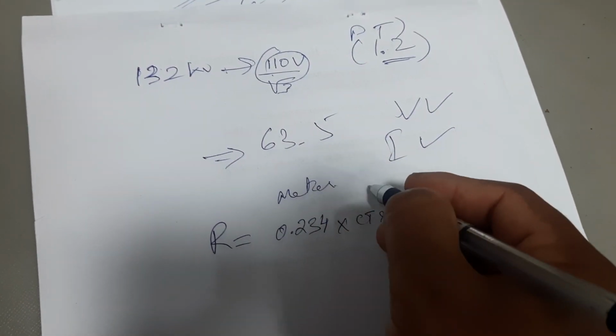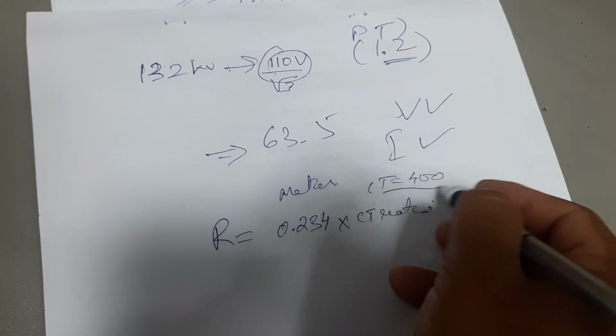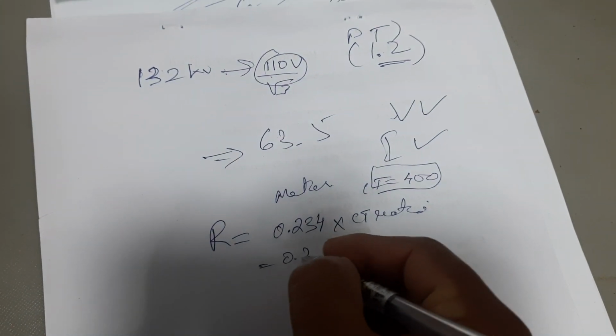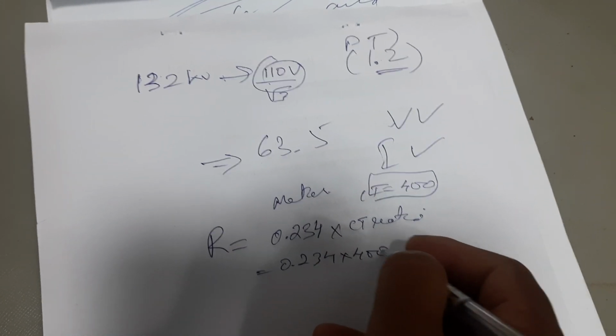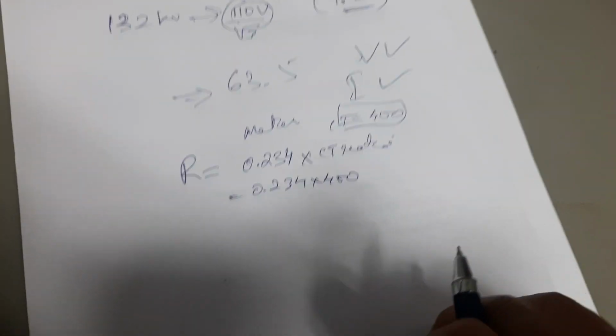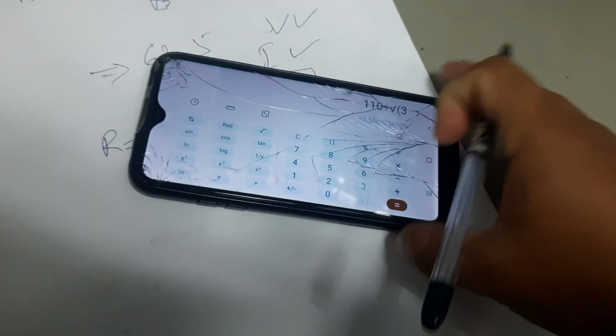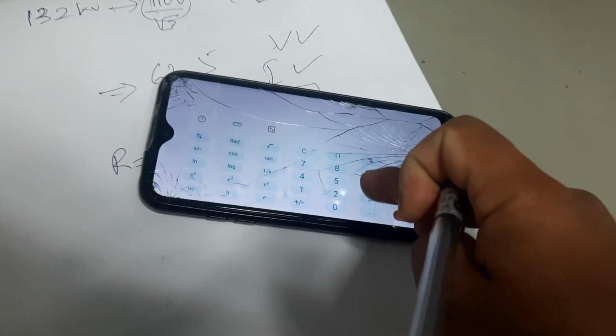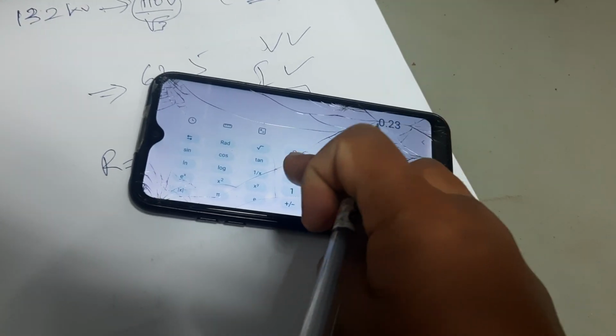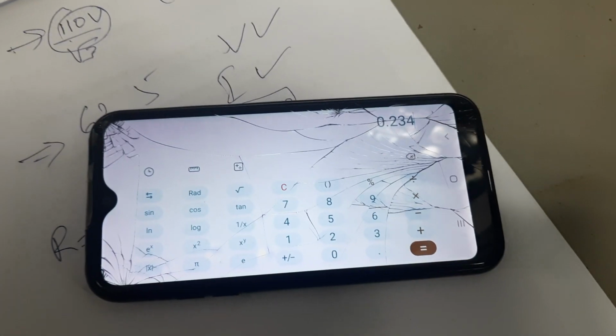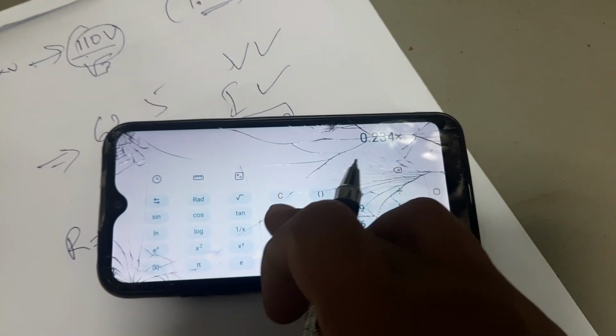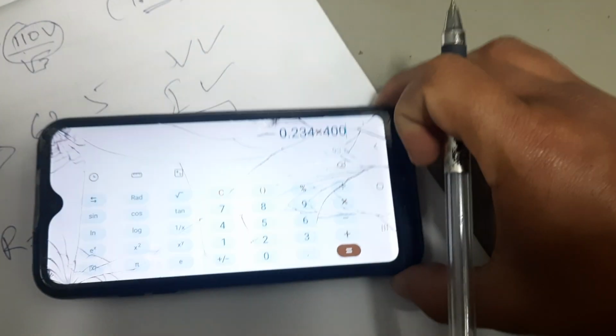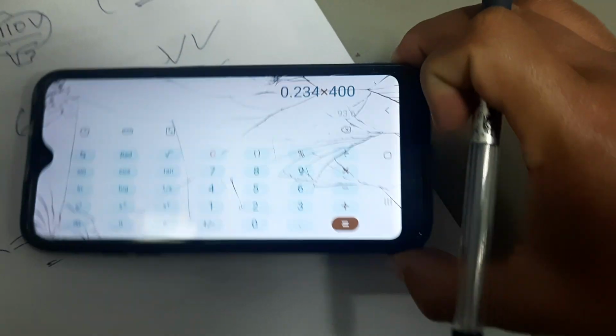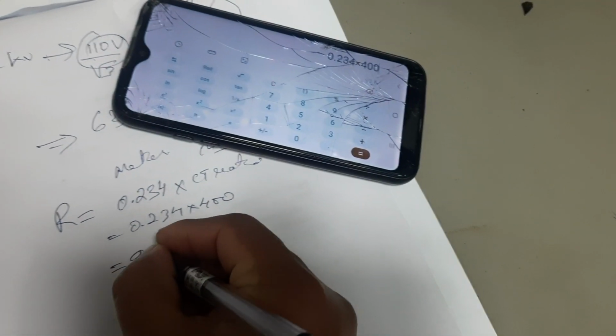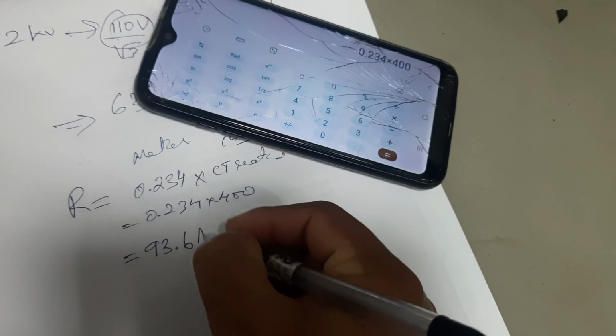Our CT ratio is nothing but 400, okay, for 132 kV. So 0.234 into 400, how much are you getting? Let us do the calculation. Okay, 0.234, if you multiply this with your CT ratio of 400, you are getting 93.6 ampere, okay, in our phase, 93.6 ampere. Okay, I'll verify this.